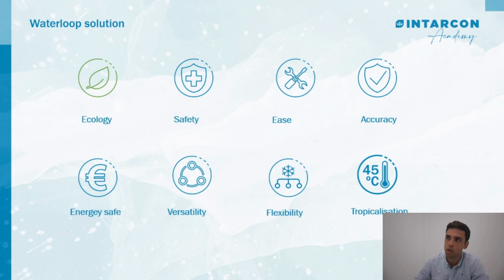Next, energy saving, use of high efficiency compressors and the use of variable flow electronic pumps and a speed controller fan in the part of the dry cooler. It provides us better energy saving. Next, versatility. In this case, it's suitable for both new installations and for the retrofit of existing installations. In addition, flexibility also keeps change to the layout of units without a major structural modification. And lastly, tropicalization, designed to work in extreme conditions of up to 45 degrees of ambient temperature.